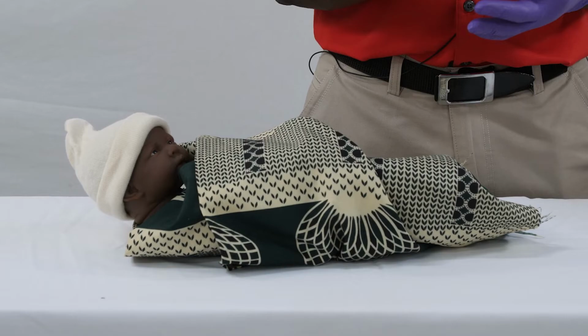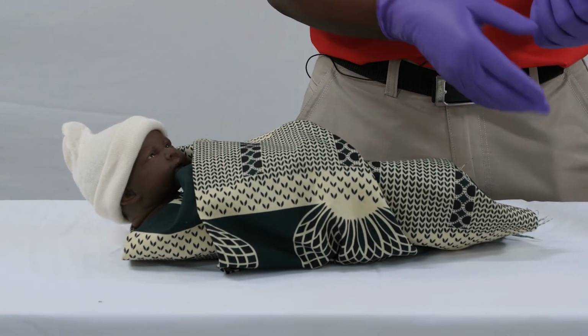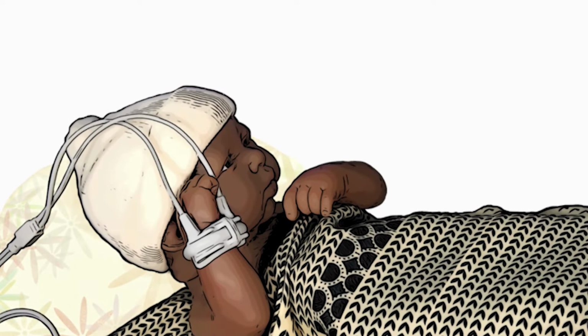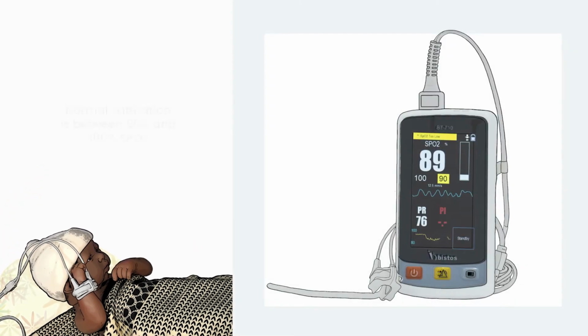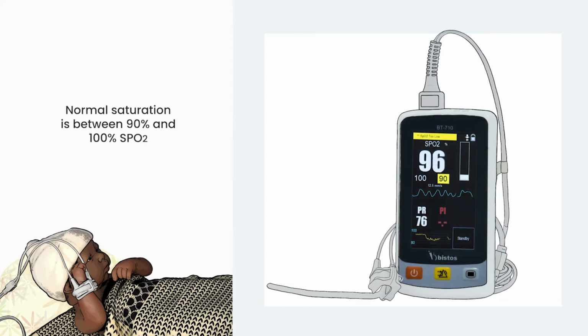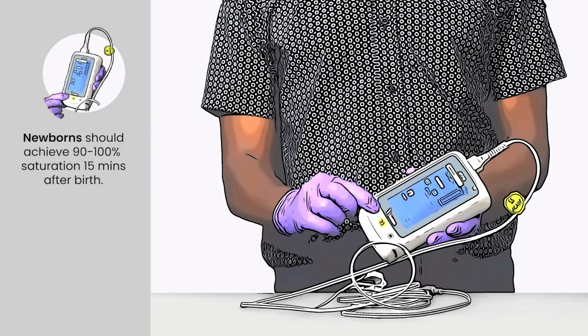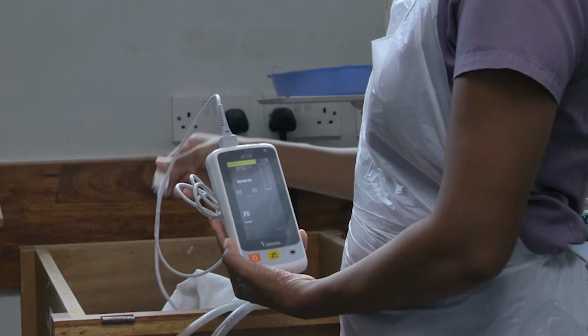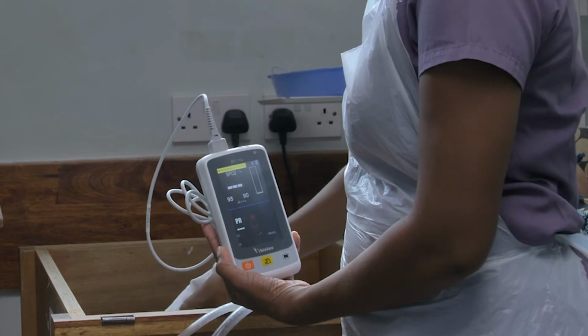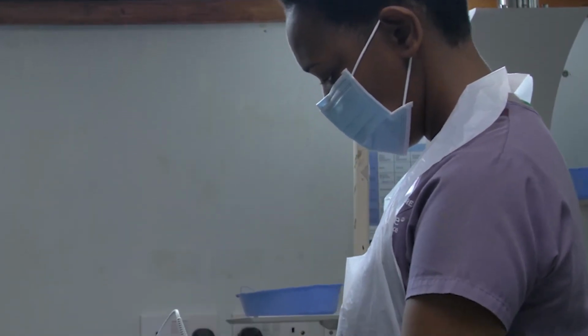They need help. Newborn babies sometimes have low saturation levels immediately after birth. But by 15 minutes after delivery, these should have recovered to between 90 and 100%. So all newborns need to be checked after 15 minutes. Pulse oximeters are also used for routine checking of all infants on admission and monitoring sick and at-risk patients afterwards. Finally, babies receiving oxygen therapy or on CPAP also need regular monitoring.